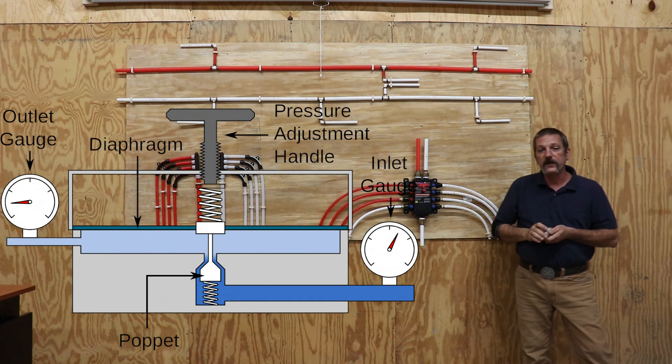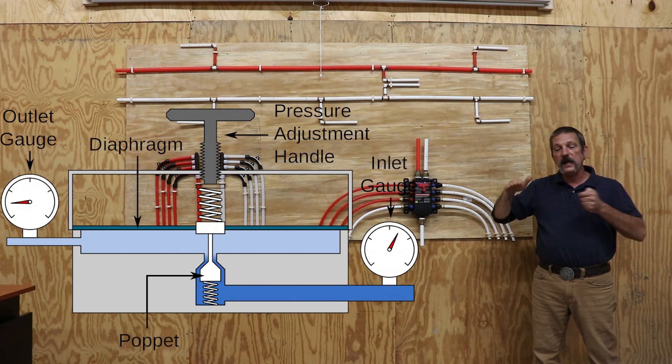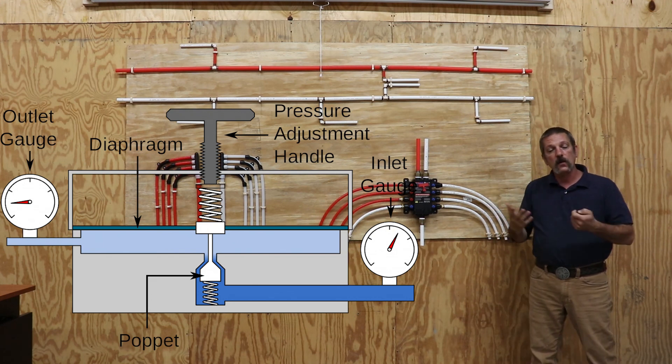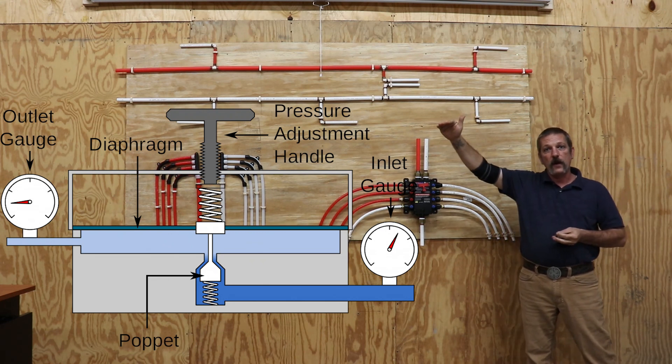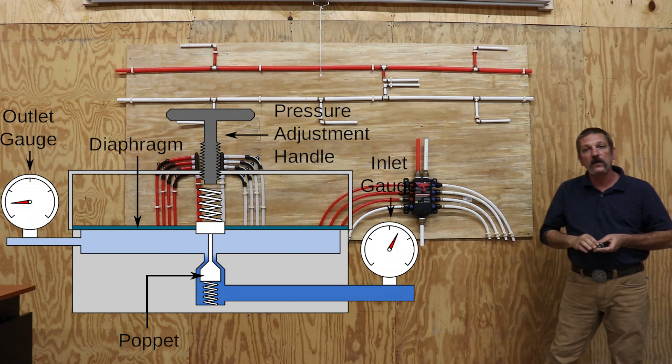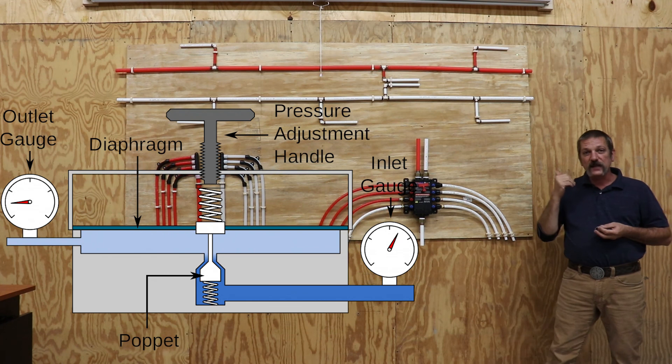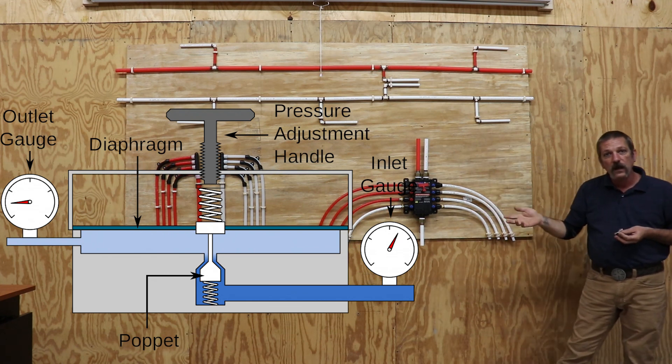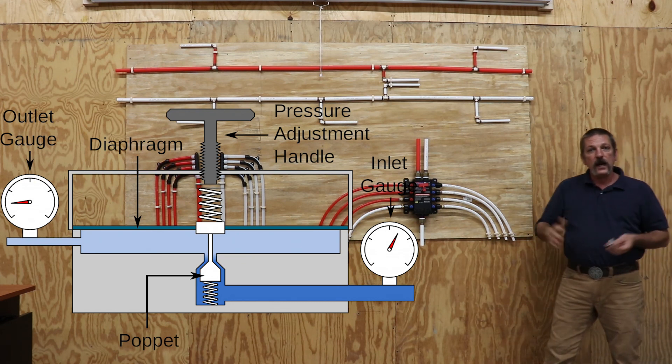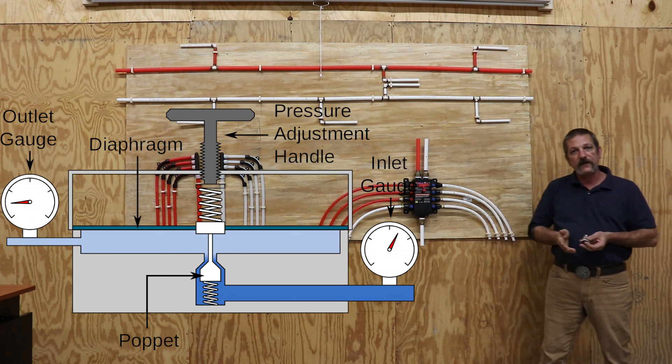Now what happens is that spring is pushing down on that diaphragm. Say it's never had any water in it and you're turning the water onto it for the first time. There's not going to be any pressure on that diaphragm. That spring is pushing it all the way down so that the poppet valve is open. Now as soon as the water comes through that poppet valve and it inflates that diaphragm it's going to balance out on that spring. And when that pressure balances out with the pressure on that spring it will close that poppet valve.